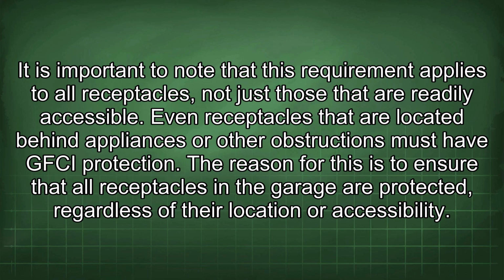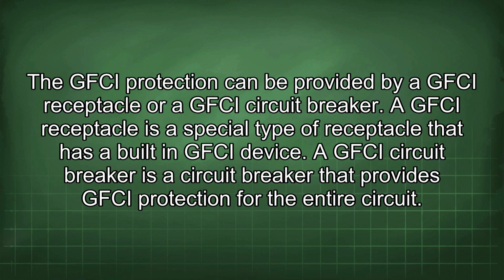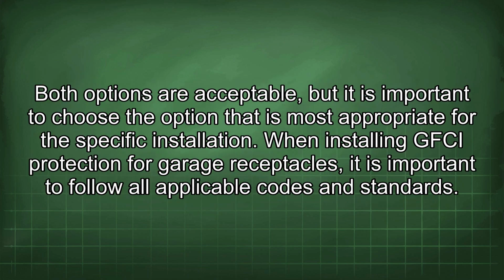It is important to note that this requirement applies to all receptacles, not just those that are readily accessible. Even receptacles that are located behind appliances or other obstructions must have GFCI protection. The reason for this is to ensure that all receptacles in the garage are protected, regardless of their location or accessibility. The GFCI protection can be provided by a GFCI receptacle or a GFCI circuit breaker. A GFCI receptacle is a special type of receptacle that has a built-in GFCI device. A GFCI circuit breaker is a circuit breaker that provides GFCI protection for the entire circuit. Both options are acceptable, but it is important to choose the option that is most appropriate for the specific installation.